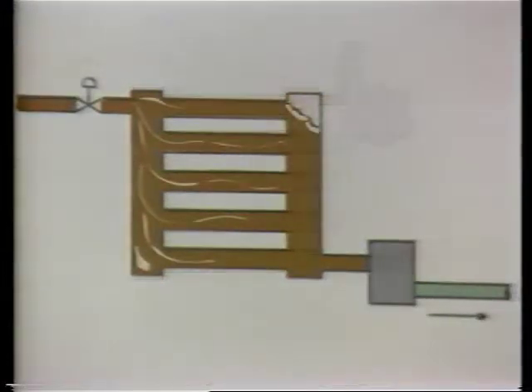Grid-type coils have a tendency to allow the formation of air pockets, resulting in non-uniform temperatures across the coil. The installation of a thermostatic air vent at the high point of the discharge manifold eliminates this possibility.